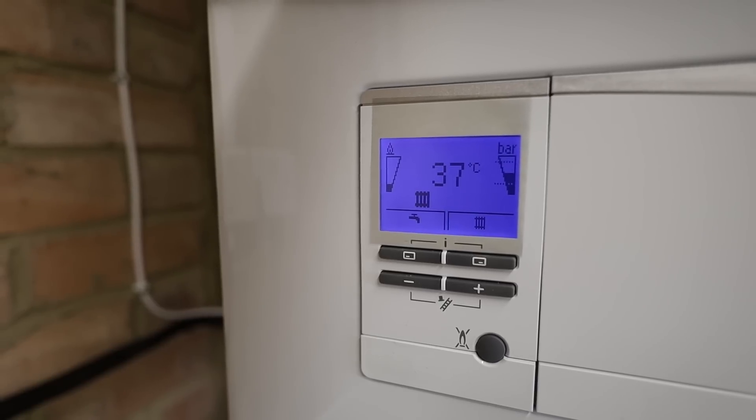The property has already been set up for a heat pump, so this boiler will run at a maximum 50°C flow temperature. With the new energy cap at roughly 3:1 — a kilowatt of electricity at around 30p and a kilowatt of gas at 10p — running this boiler at such a low flow temperature will cost around £1,600 a year at this property. Running a heat pump at 40°C flow will cost around £500–700 less, so that's roughly a 40% saving.